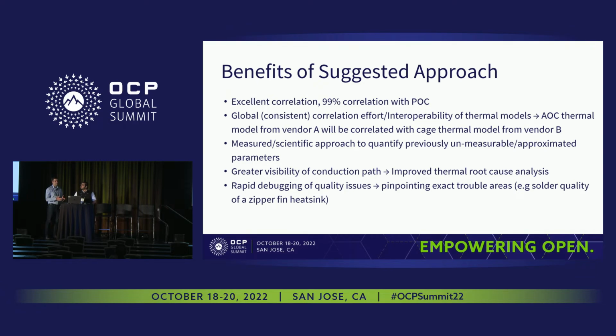So the measurement itself has two error sources. One is the electrical measurement part. There we are very repeatable and reproducible, and the error is very, very small. So we can measure 4 microvolts of change with pretty good accuracy. When it comes to calibration, there's another calibration step when you get the voltage to temperature characteristics of your component. That depends on your thermal environment. That can be maybe 3% error maximum. Gotcha. Thank you.